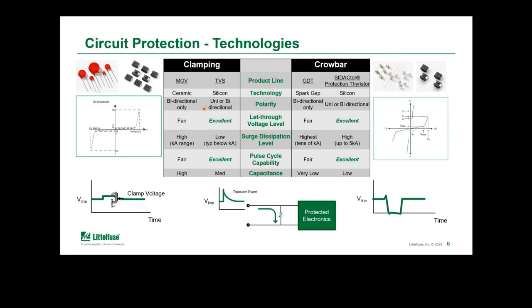Now, as far as their capabilities are concerned, they do have some advantages and disadvantages, and I'm going to highlight a couple here. The first one is the let-through voltage. So how well is it protecting? How tightly is it clamping? MOVs have a somewhat higher clamping voltage, and GDTs take a while to get going and will have a high let-through before they crowbar into the crowbar state.